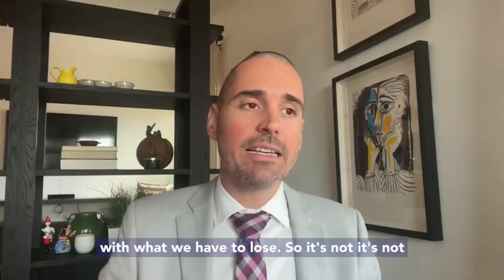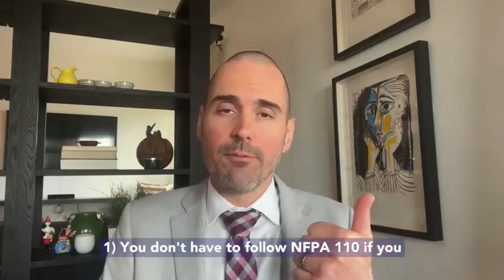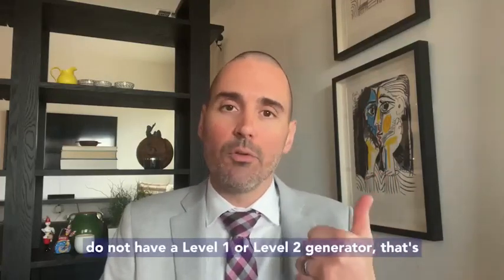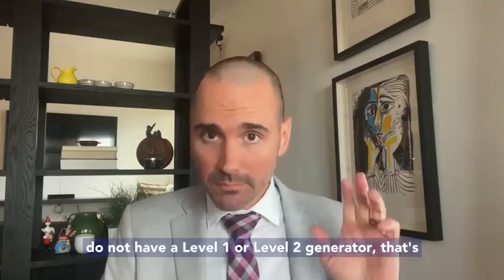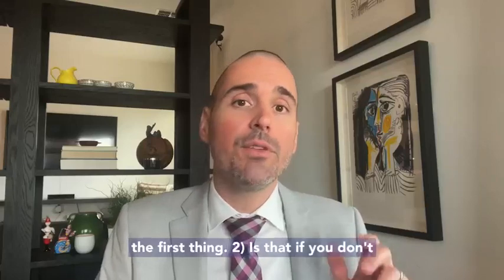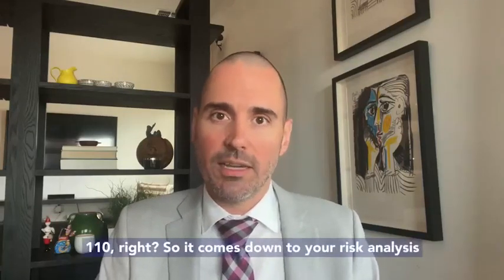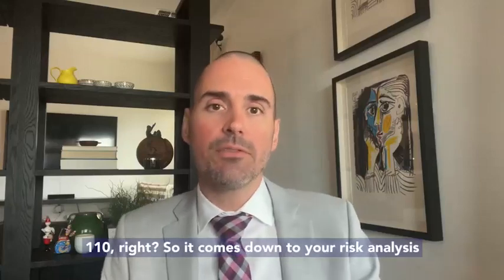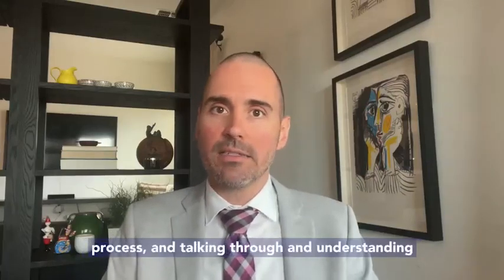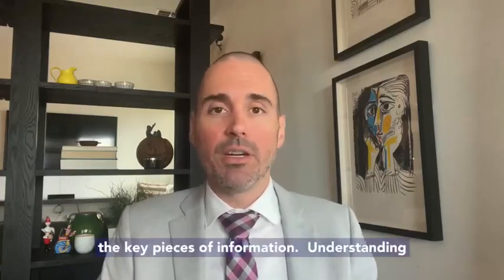So it's not always just because we don't have to. Number one, you don't have to follow NFPA 110 if you do not have a level 1 or level 2 generator. That's the first thing. Number 2 is that if you don't have to follow 110, should you still follow 110? So it comes down to your risk analysis process and talking through and understanding the key pieces of information.